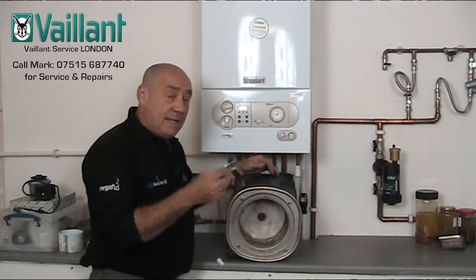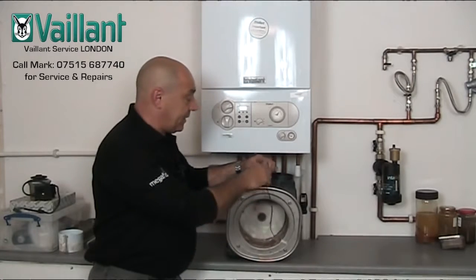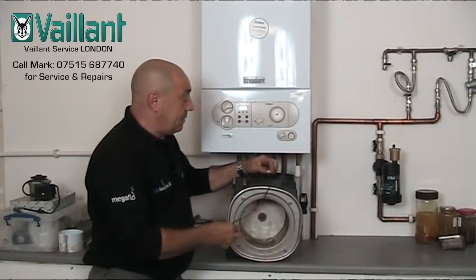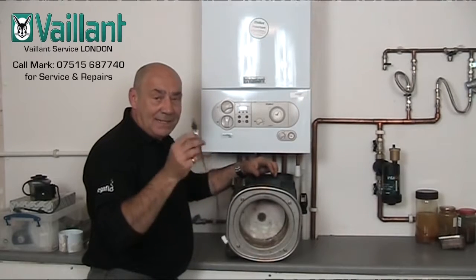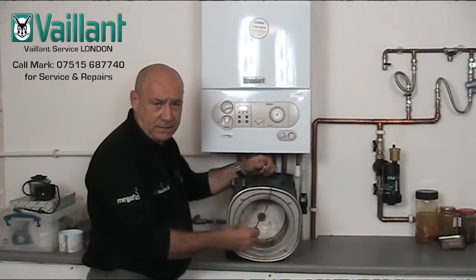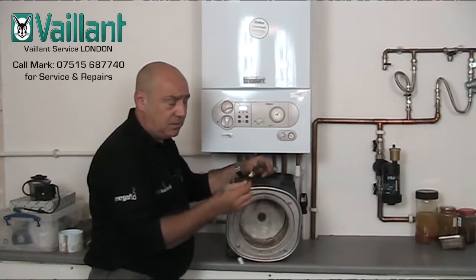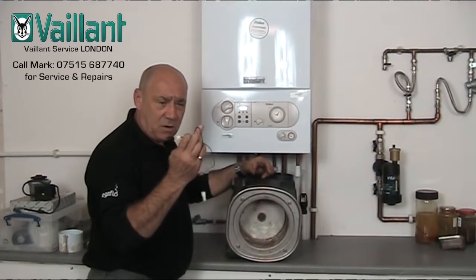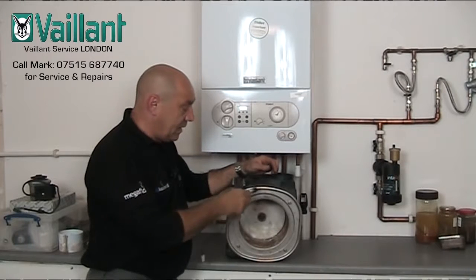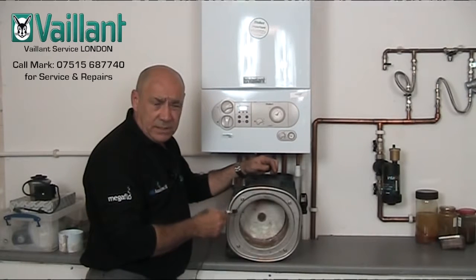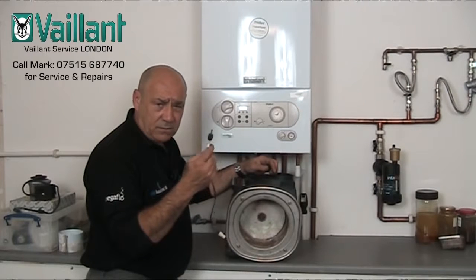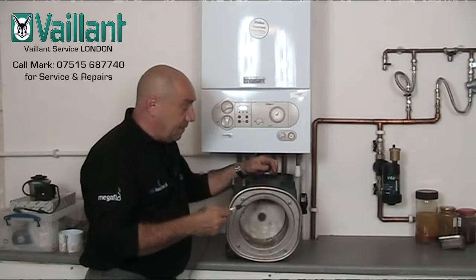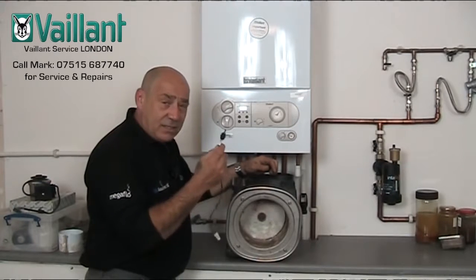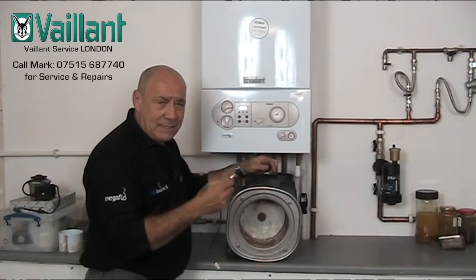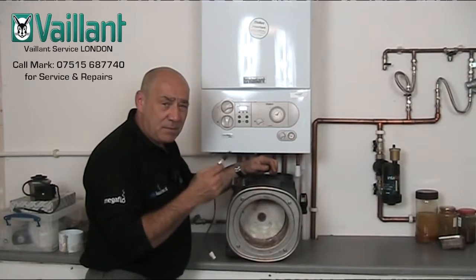So if you've got an F76 fault code, you need to check, or this will probably be the problem. Now, it's worth getting it checked out by someone who knows what they're doing. Get them in to check that it isn't the actual linkage that's the problem, or a wiring defect, because you could be fooled. If you've got a break in the wiring of the link, it will give you an F76 fault code. It won't necessarily mean that the heat exchanger is faulty, nor does it mean that the thermal link has tripped. So it may be something very simple. But if you have all that checked out, and this has actually gone, then you will need to buy a new main heat exchanger.